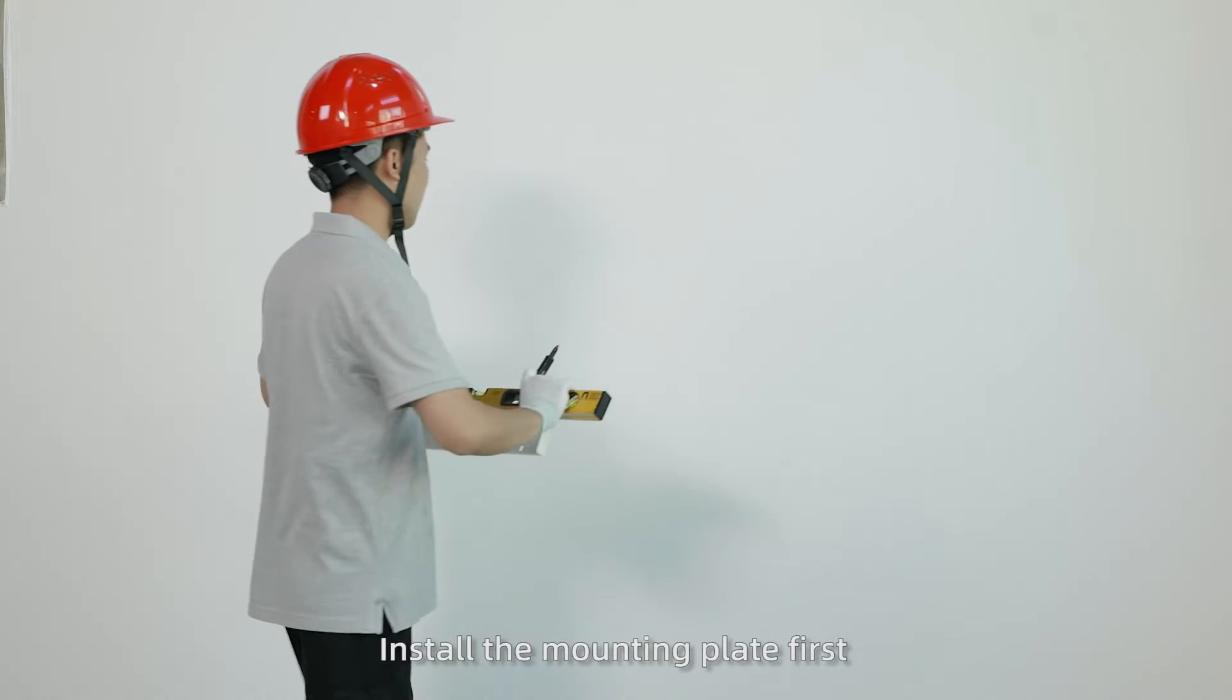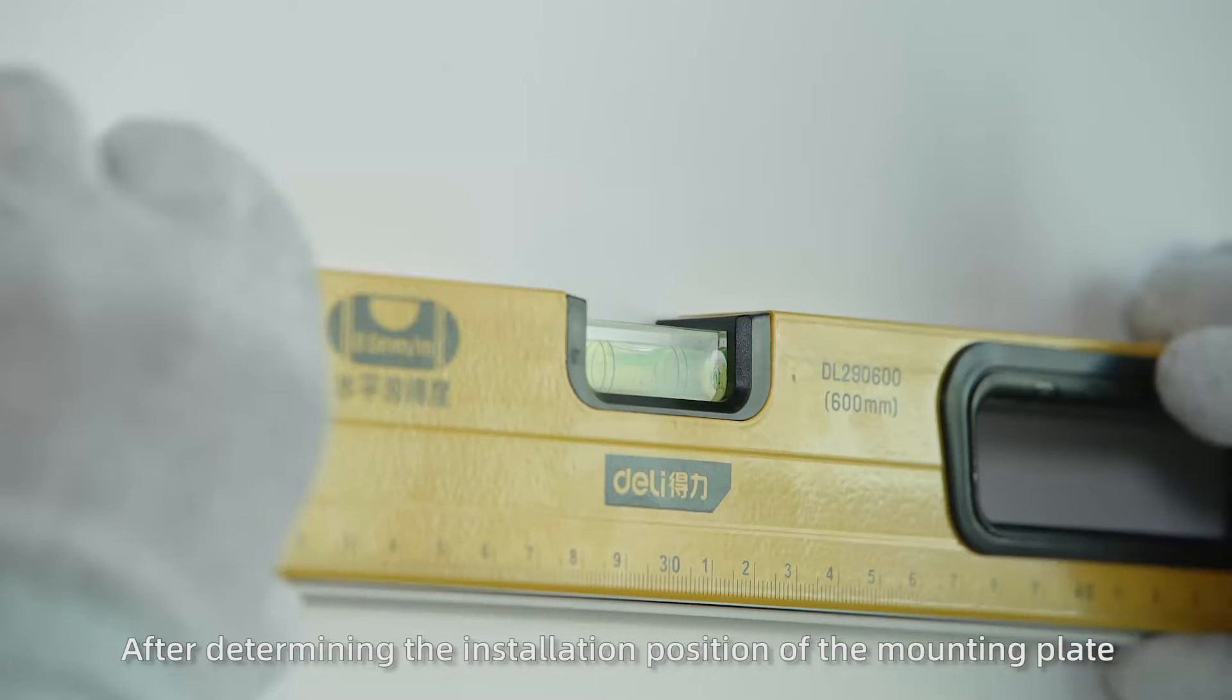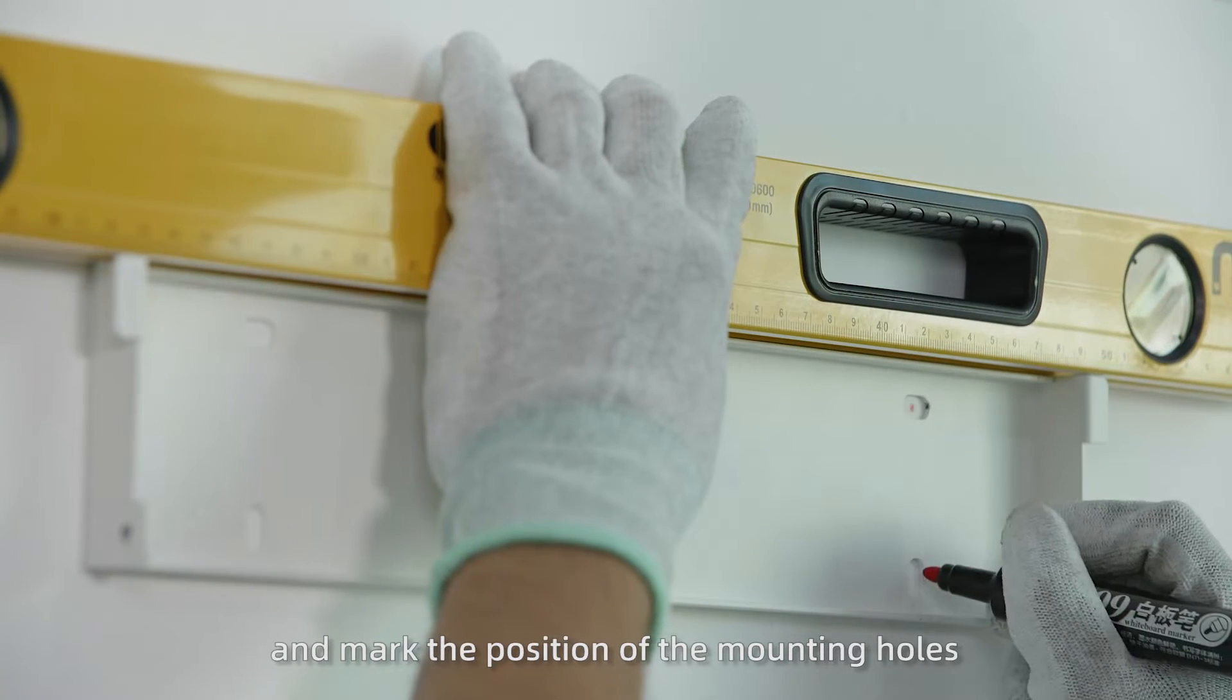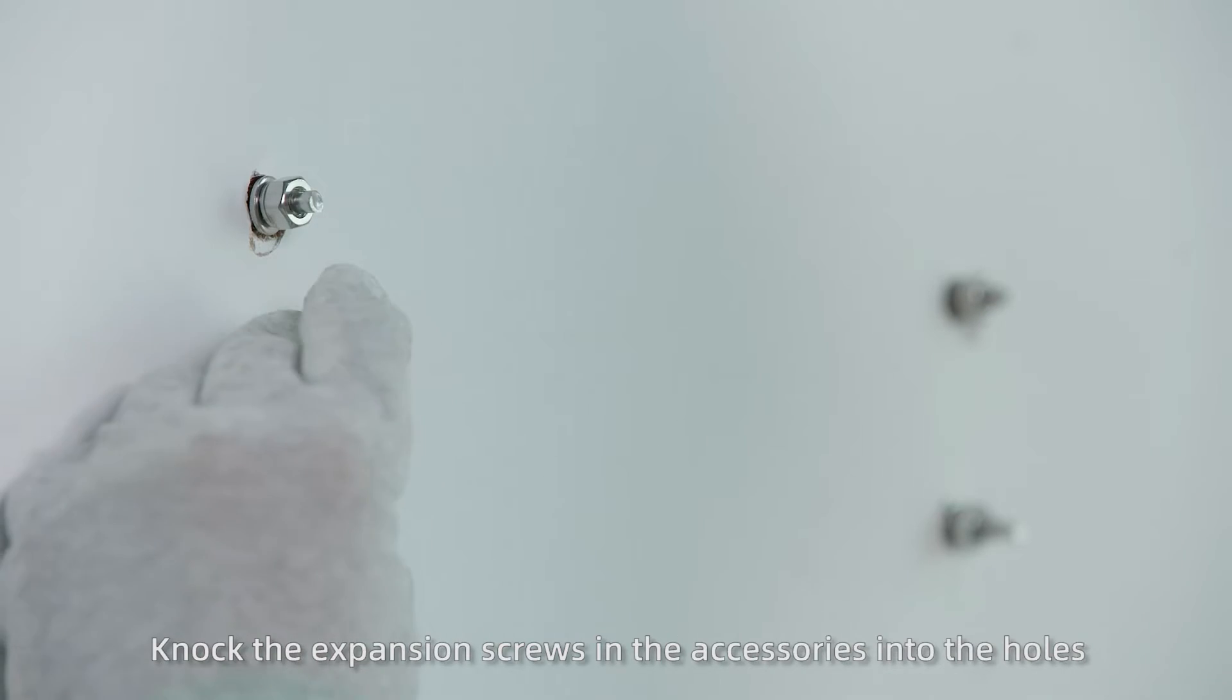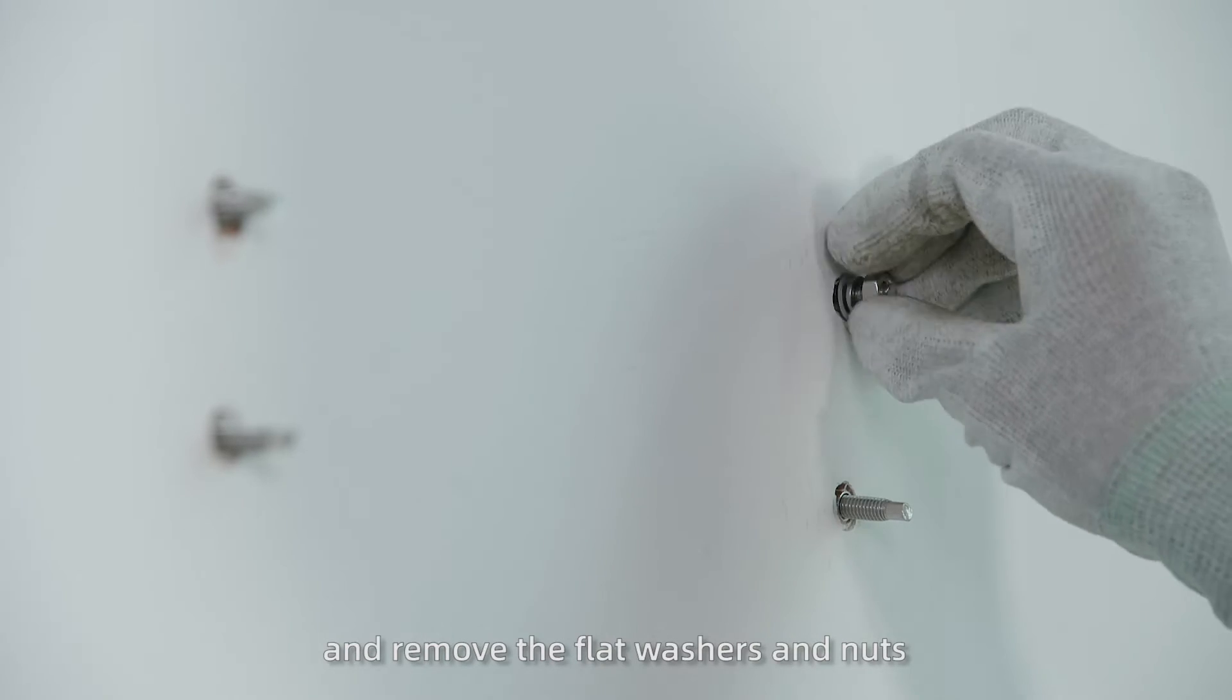Install the mounting plate first. After determining the installation position, use a spirit level to ensure balance and mark the position of the mounting holes. Then punch holes on the wall or bracket with an 8 mm electric drill, and the hole depth should be more than 45 mm. Knock the expansion screws into the holes and remove the flat washers and nuts.